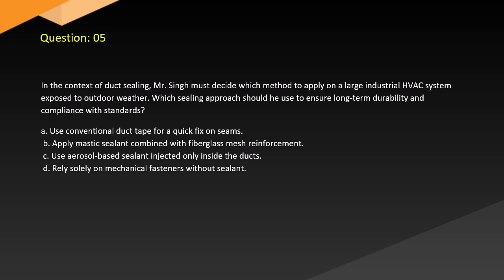A. Use conventional duct tape for a quick fix on seams. B. Apply mastic sealant combined with fiberglass mesh reinforcement. C. Use aerosol-based sealant injected only inside the ducts. D. Rely solely on mechanical fasteners without sealant.